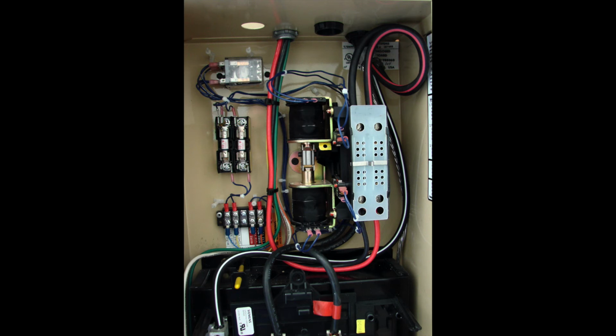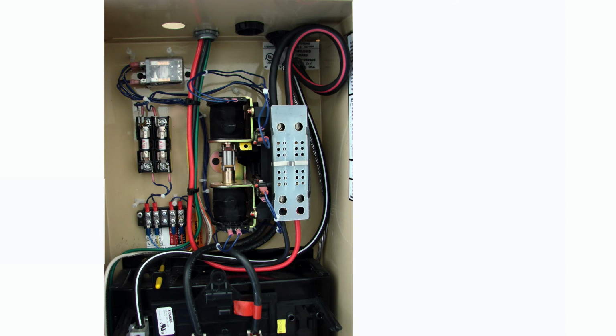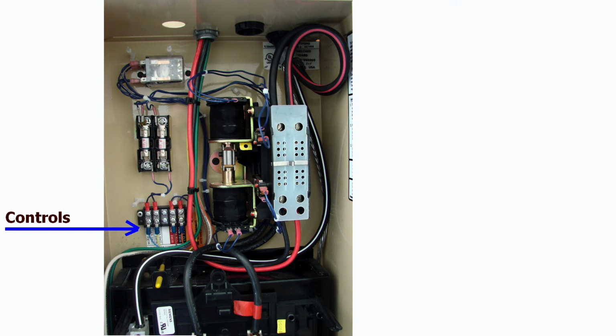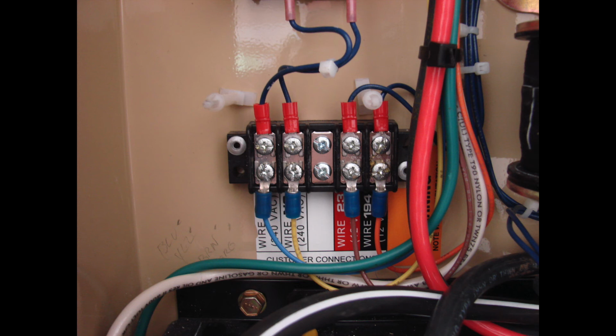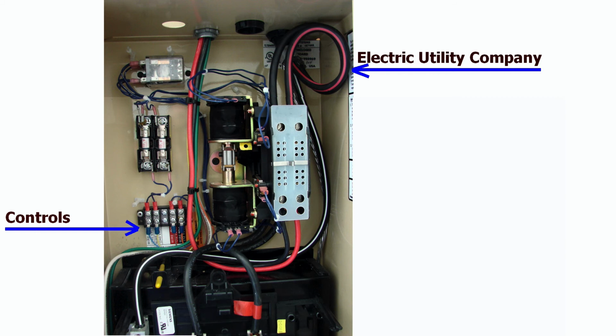Now you'll see in this transfer switch, again, the components are pretty much straightforward and generic for most transfer switches of this size. We've got our terminal block there for the control wiring to be attached, and in this case we've got just a few wires there, 4 wires, and then we are attaching the wiring for the electrical utility from the main panel, which has not been connected at the panel, of course. So these wires are not energized.